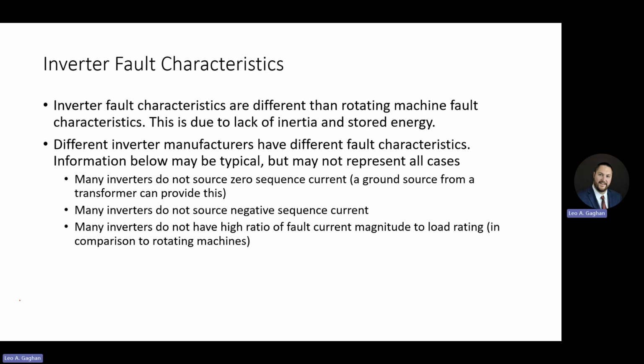So one consideration is many inverters do not source zero sequence current. They're actually usually separated by a delta-Y transformer at the pad mount level that goes from low voltage to medium voltage. So usually separated on the zero sequence. If we want to add a ground source from a transformer with a Y grounded winding up on the distribution side, we can do that to kind of fix that problem.